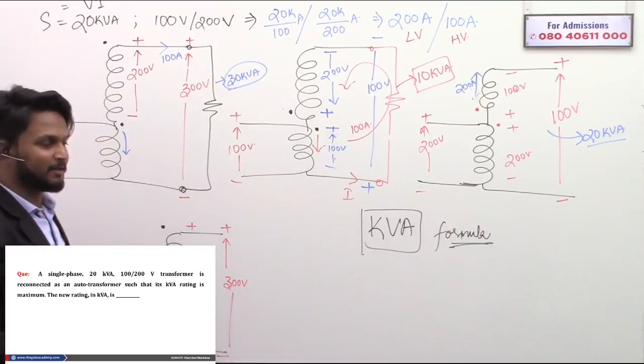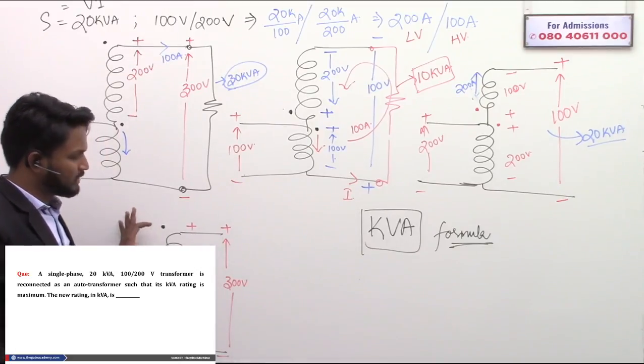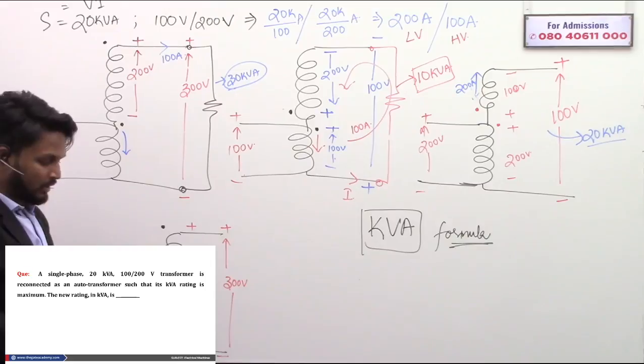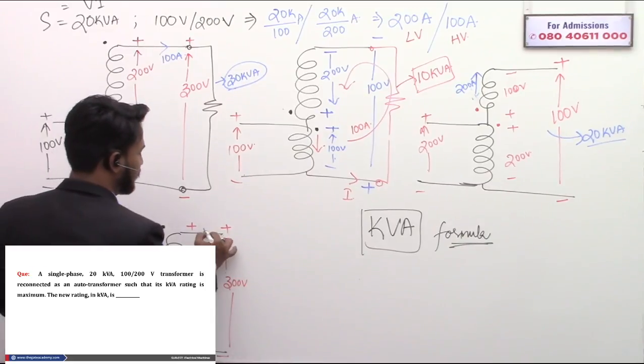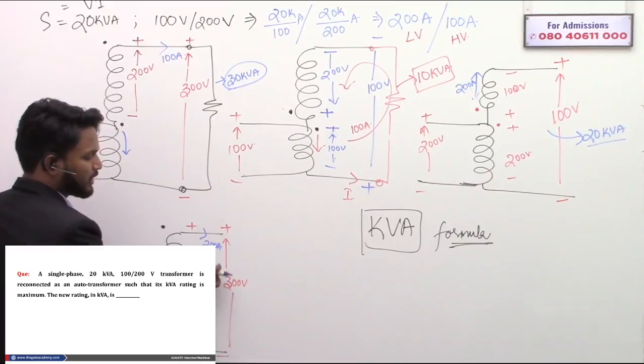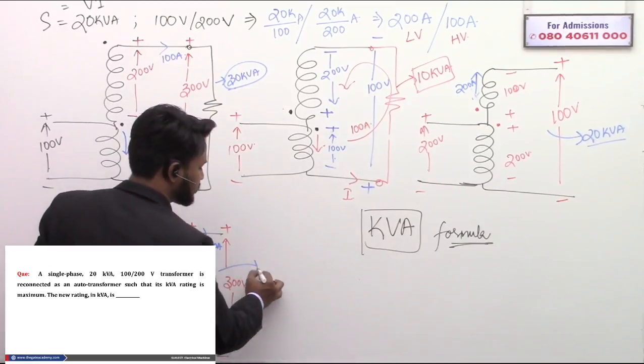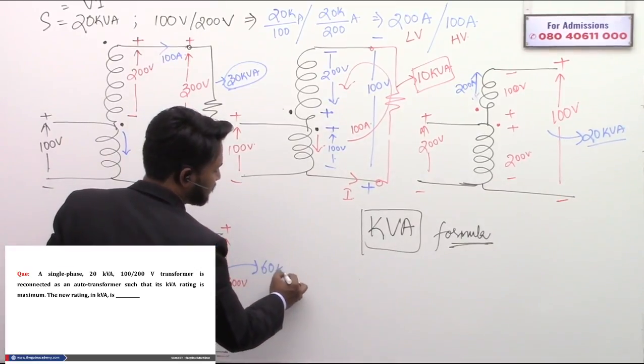Now look at this configuration. This 100 volts winding can carry 200 amperes of current. The rating is 300 multiplied by 200, which is 60 kVA.